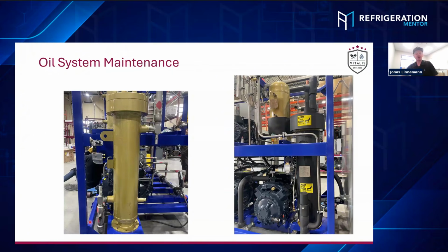And I always prefer a little trick to drain the CO₂ as well as possible. Once you have isolated these 2 main isolation valves, you could just put a magnet on this little oil return valve and then drain all the oil and most of the CO₂ vapor into the oil reservoir. And once the pressure is equalized, you can just shut off this oil return line as well. And then you just drain half of the CO₂, right?